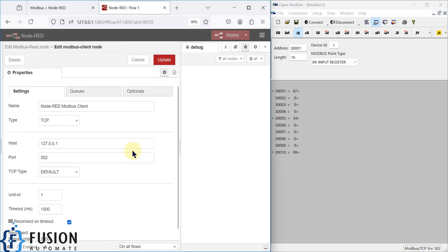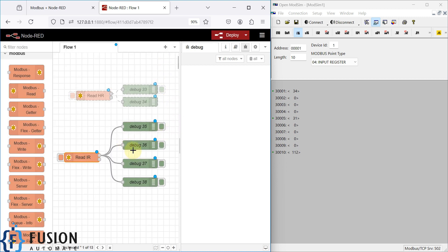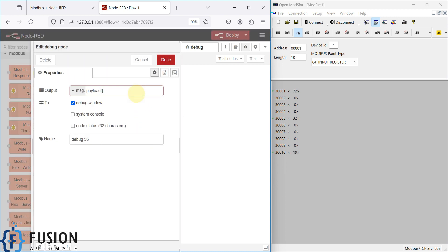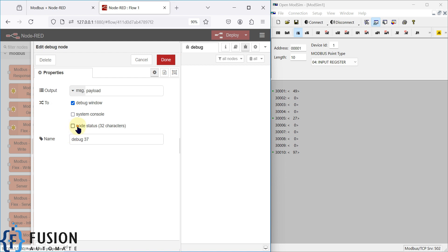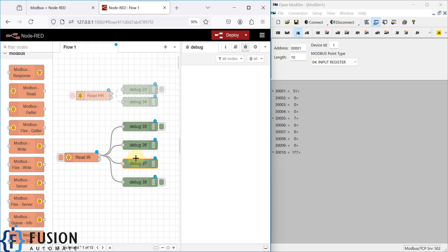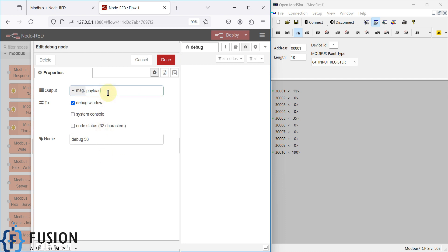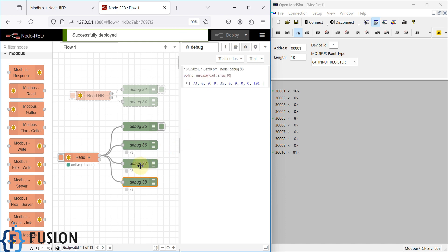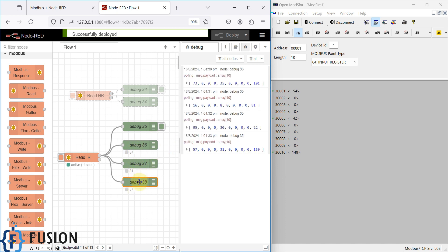We are going to use the same Modbus client because the IP address and port number haven't changed — it's localhost on port 502. I'll press done, and configure the debug nodes: the first will print the first input register value in the node status, the second will display index 4 (zero, one, two, three, four), and the third will display index 9.